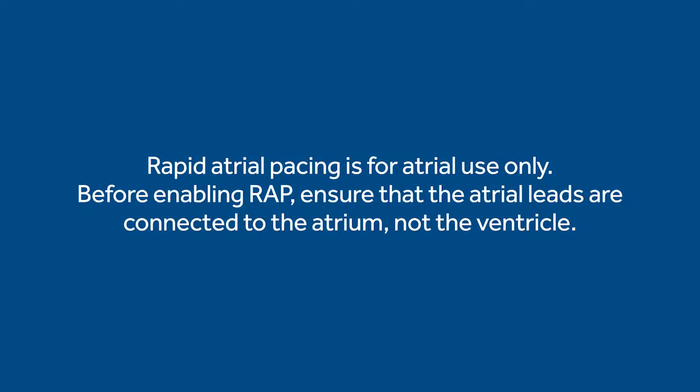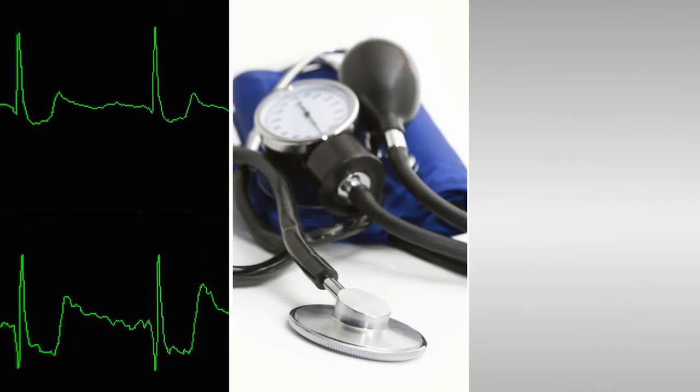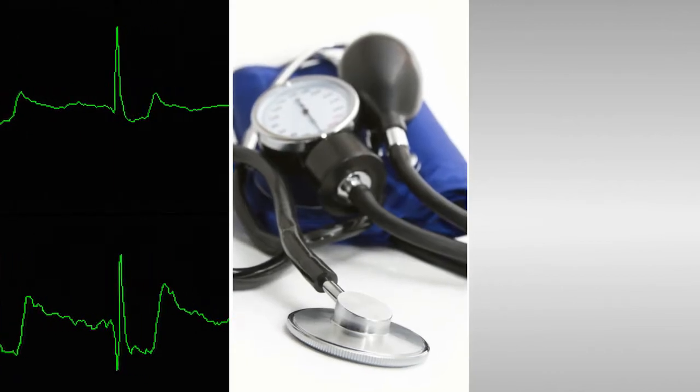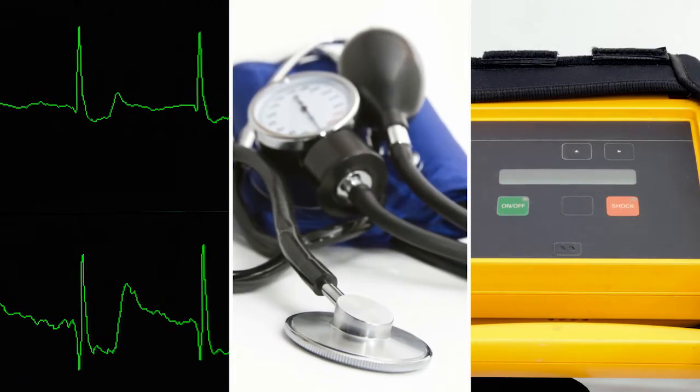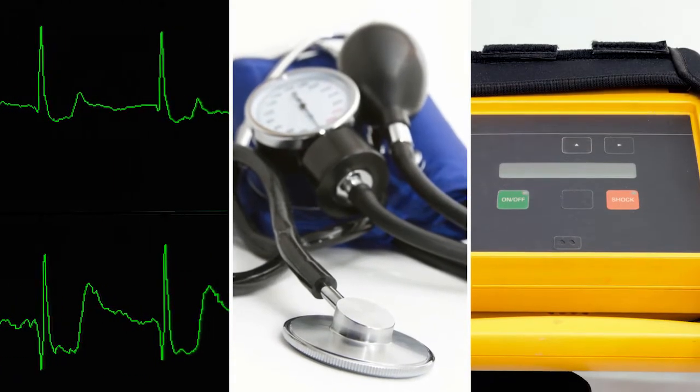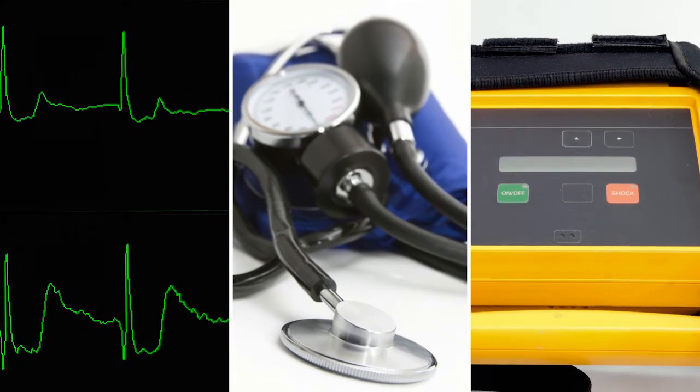Rapid atrial pacing is for atrial use only. Before enabling RAP, ensure that the atrial leads are connected to the atrium, not the ventricle. Also, monitor the patient's ECG and blood pressure, and ensure that defibrillation equipment is immediately available.